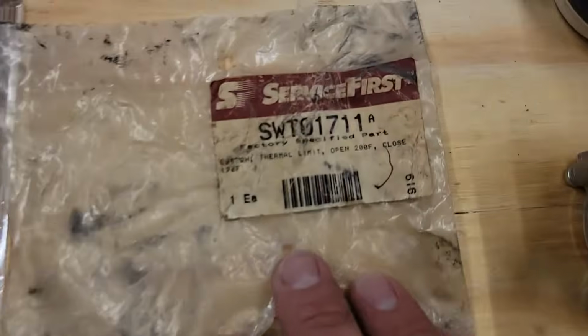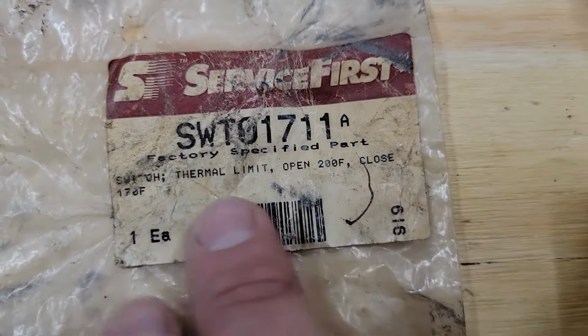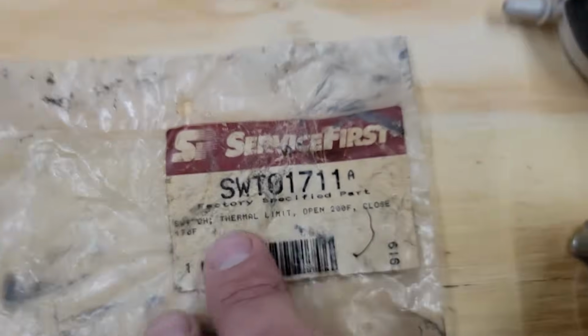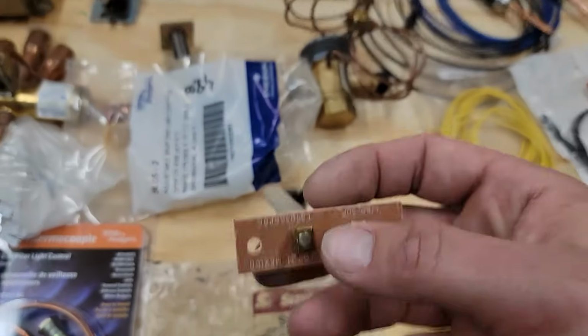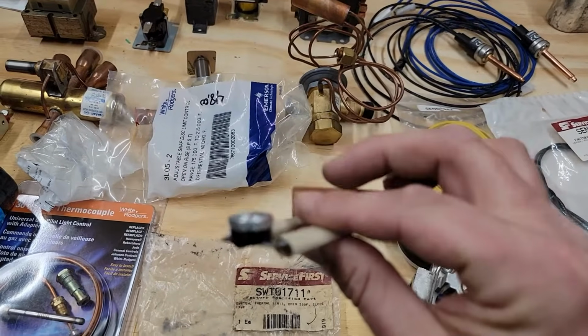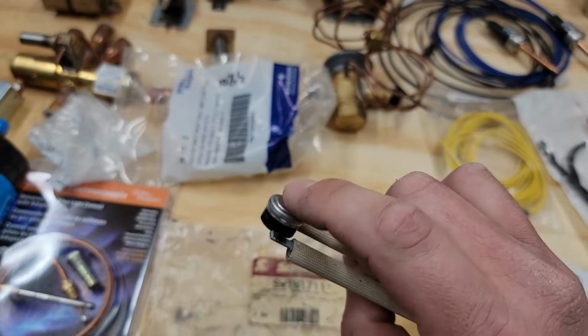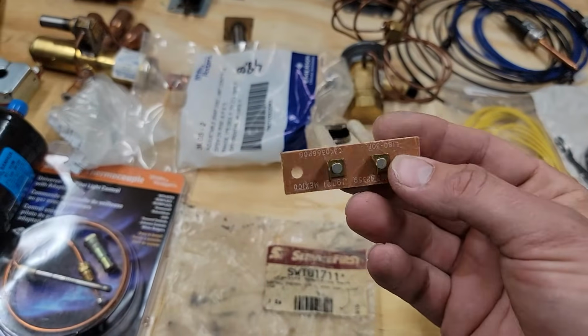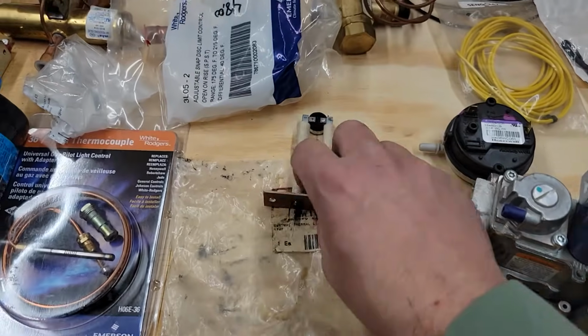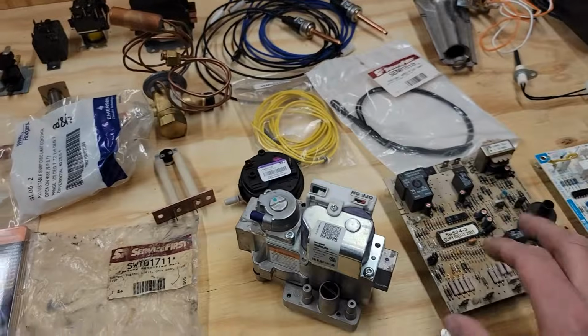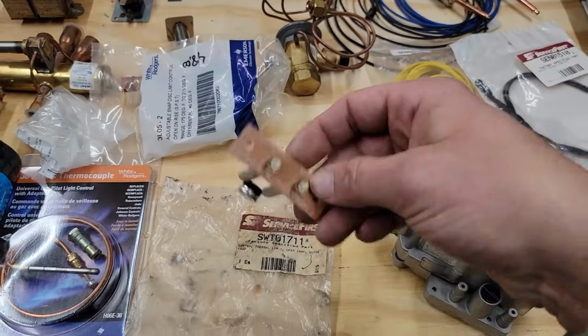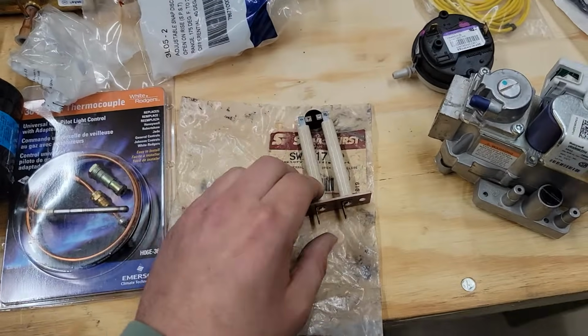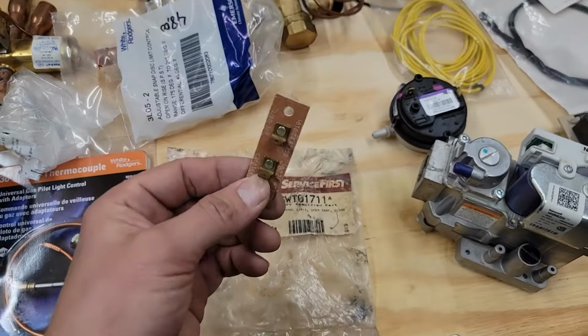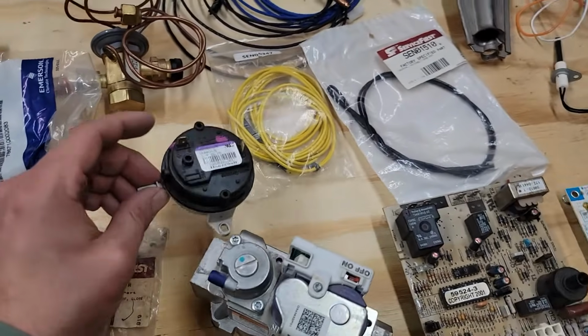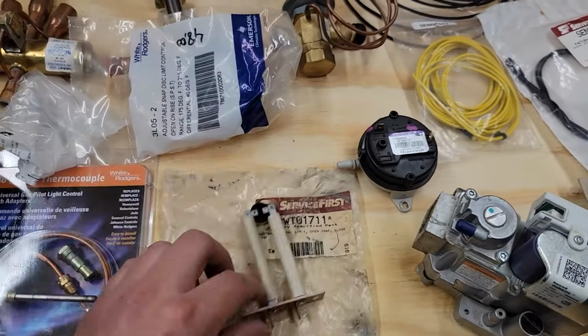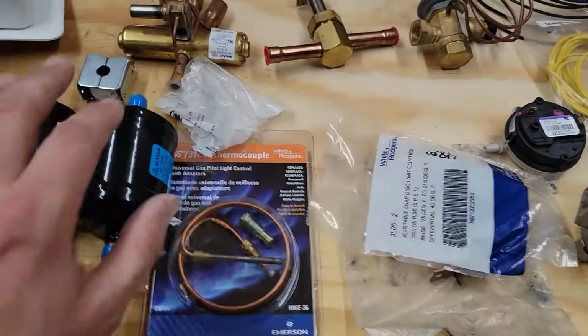All right, so let's look at this. It says open 200, thermal limit, close 170. So right here, this is mounted in the area where the heat exchanger is, and when it gets hot, of course, this right here will open the circuit. So then, of course, the unit will no longer be heating, and then, of course, it will probably cause the indoor fan to run so that it cools it down. So this is a good safety. This is also a safety. This is a safety for the inducer. This is a safety for your furnace. All right, let's keep going.